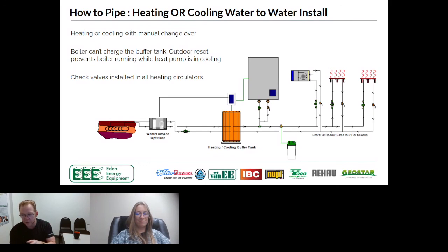We're talking about this. So if the return temperature is higher than 140, it's going to be a problem. A lot of equipment is smart enough to figure that out. Like I can tell you for a fact, the IBC unit will shut itself off. The Enertech and the System M, I can't say for sure that they will shut themselves off. But part of what we do here at Eden is every single product that we see, wherever possible, we install them in the lab, we play with them. And the reality is we intentionally try to break them. We will do to this equipment what we know people will do, and we give that feedback back to the manufacturers. And manufacturers do care.